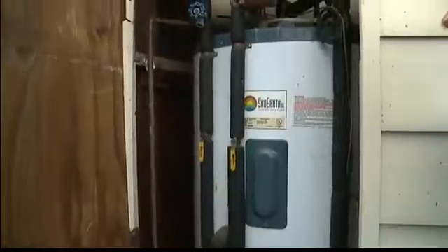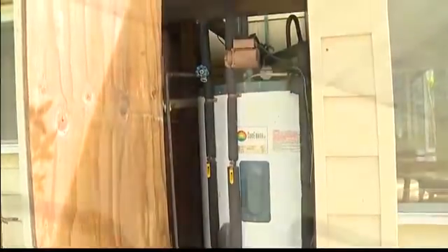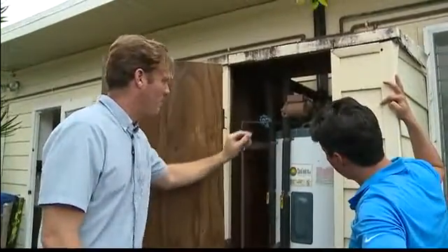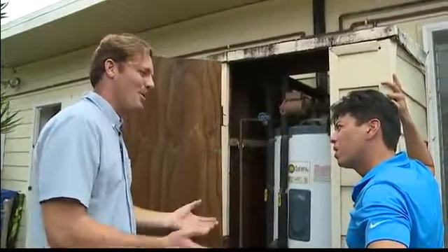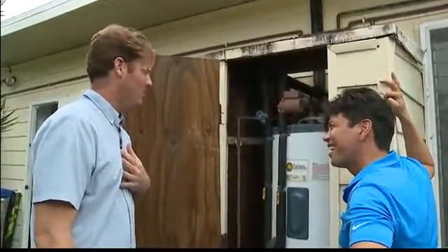This is fairly typical to what most people have in Hawaii. You've got all of these pipes — almost like you really can't even see the tank. I'm looking right here and I see about 11 valves. Basically all of this is necessary to take the cold water that's in the tank and pump it up to the roof to the collectors. It then gets warm and comes back down. You've got a series of check valves and ball valves to ensure if anything happens you can close it off for maintenance. But most people don't know what to do with it, and when I look at this, all I see is points of failure.